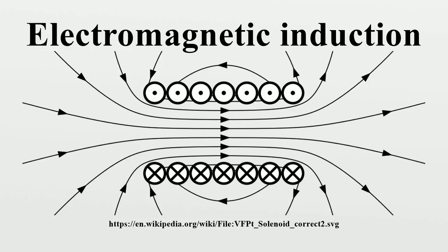Magnetic flow meter. Faraday's law is used for measuring the flow of electrically conductive liquids and slurries. Such instruments are called magnetic flow meters. The induced voltage generated in the magnetic field B due to a conductive liquid moving at velocity v is thus given by the equation, where ℓ is the distance between electrodes in the magnetic flow meter.